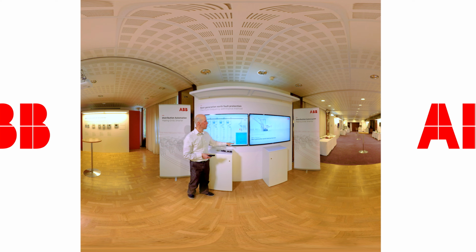This current is then compensated by the Petersen coil. Normally the compensation degree used is slightly undercompensated, and the coil current is about 50 amperes. From an earth fault protection perspective, there is a very important component in addition to the Petersen coil.